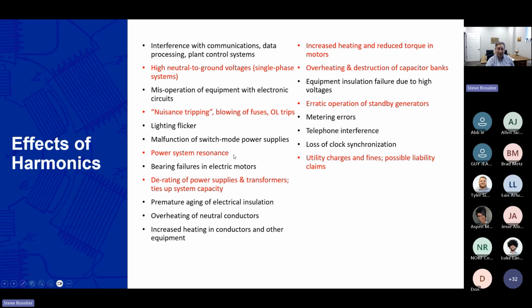System resonance. If you've got power factor correction capacitors in a system and it's been working great for 20 years, and now you add a variable frequency drive, that fifth harmonic, 300 hertz, or seventh harmonic, based on the system impedance, can easily resonate with capacitors way upstream, and even in some cases with utility capacitors. So system resonance, overheating, easy destruction of capacitors, blowing of fuses, all those things have been very prevalent as we've looked at more and more ways to mitigate harmonics and where the susceptibility is going to be. Power factor correction is certainly one of those.